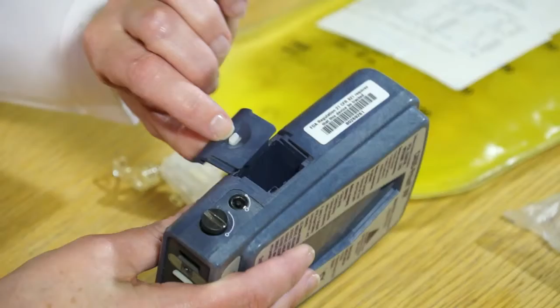Add the 9-volt battery to the battery compartment of the CADD. This battery must be in the pump and the battery pack used because of the high volume being infused. This will avoid you getting a low battery alarm during the infusion and causing an interruption of therapy. The battery pack will not work if the 9-volt battery is not in.